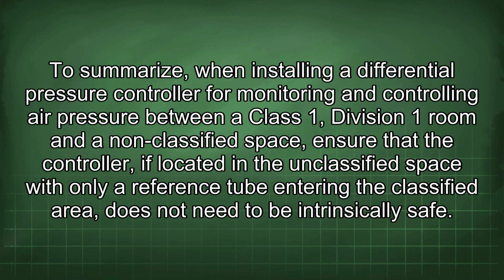To summarize, when installing a differential pressure controller for monitoring and controlling air pressure between a Class 1, Division 1 room and a non-classified space, ensure that the controller, if located in the unclassified space with only a reference tube entering the classified area, does not need to be intrinsically safe.